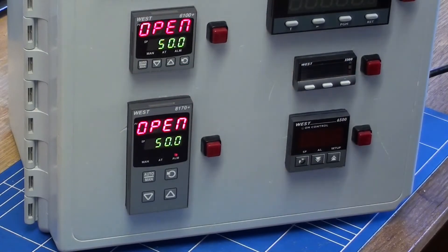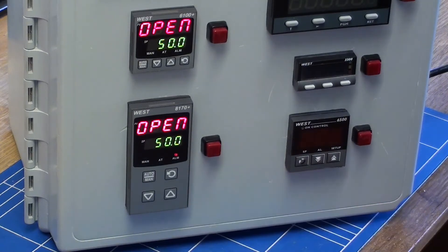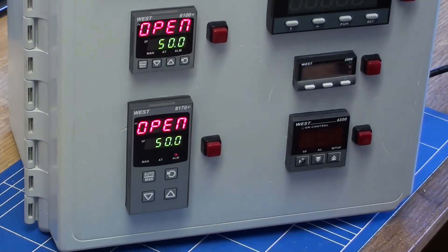It is possible to link up controllers that have the digital input boards fitted. For example, here I have a 16th DIN controller P6100 and an 8th DIN controller P8170, and they both have the digital input boards fitted. I have set set point one at 50 and on both of them set point two at 200. By flicking the switch, both set points change over from set point one to set point two.